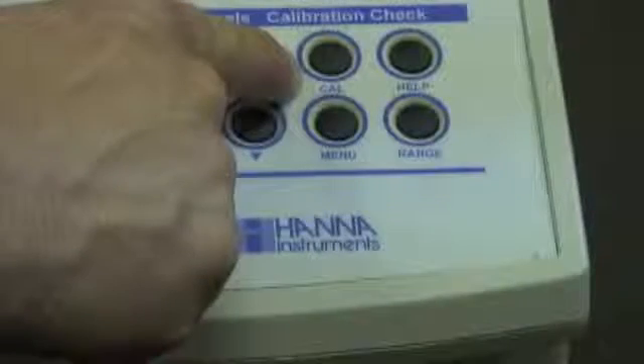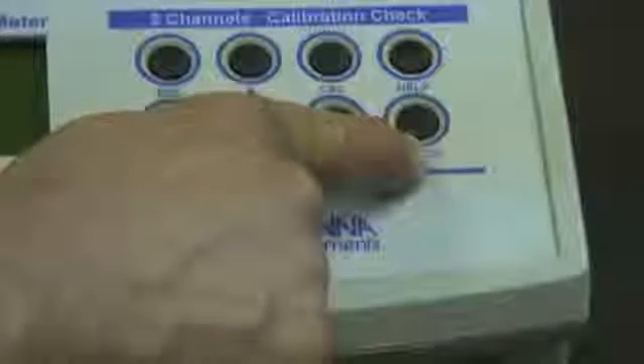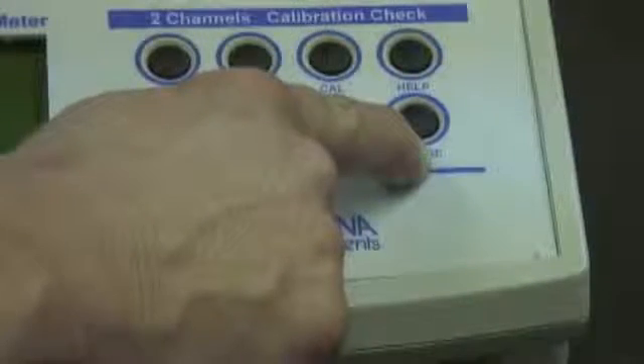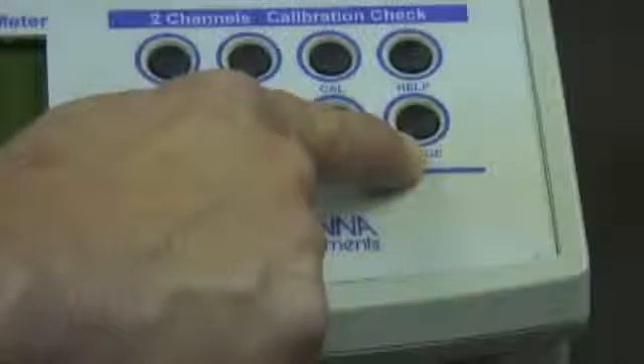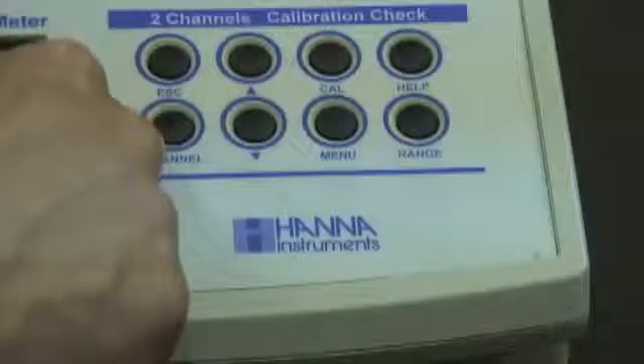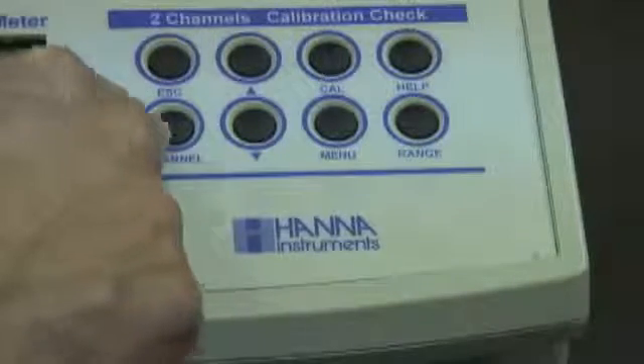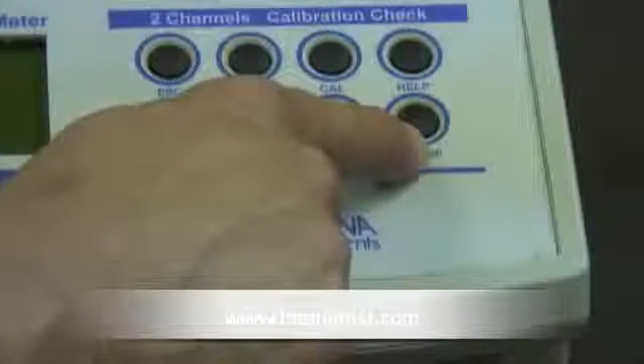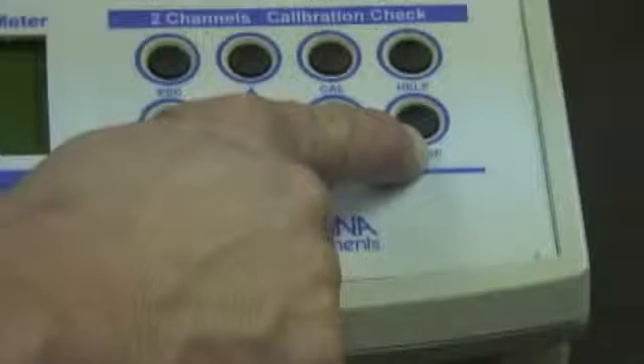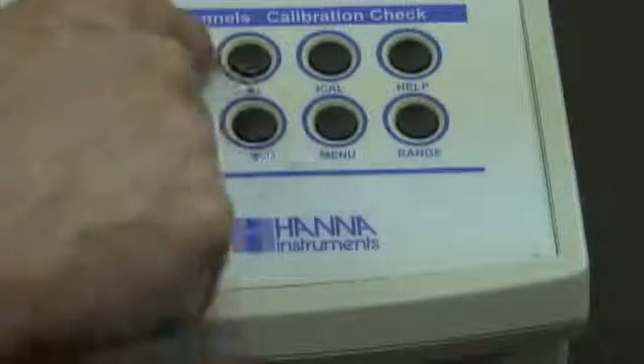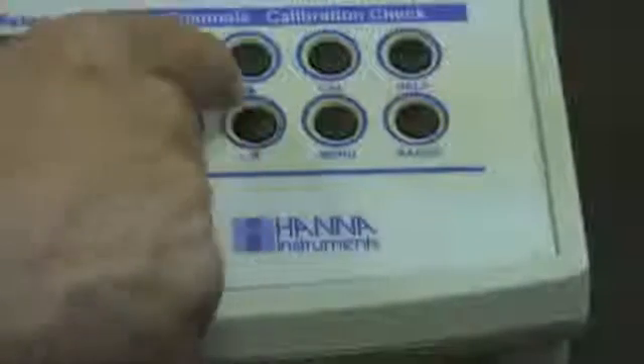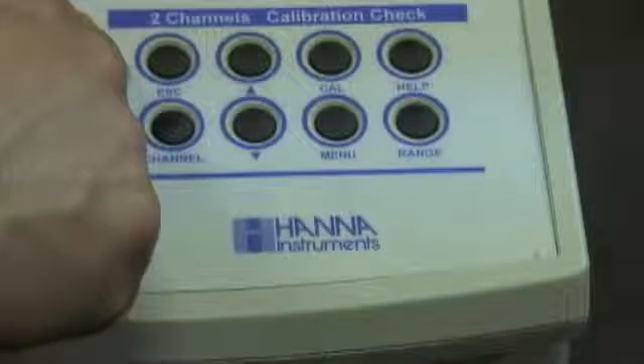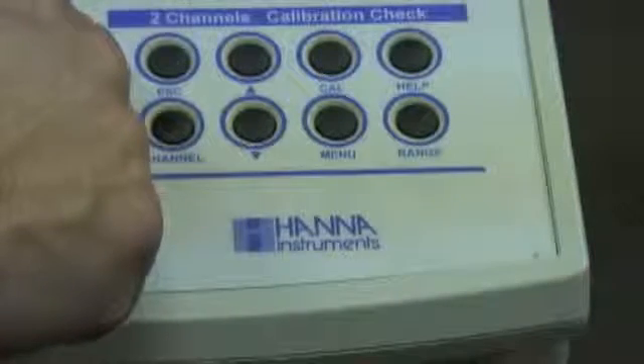Calibration button, that takes you right into the calibration mode. And then the range button. For example, if you're on channel 1 and you want to go back and forth between pH and millivolts, you simply hit the range button. And then when you hit the channel button and you go to channel 2 and you want to switch back and forth between ISE and millivolts, you do the same thing by pushing the range button. We have a menu button which displays information for the virtual keys, simple up and down buttons which moves you around the screen depending on what mode you're in, and then an escape button if you ever need to back out of a particular screen that you may be in.